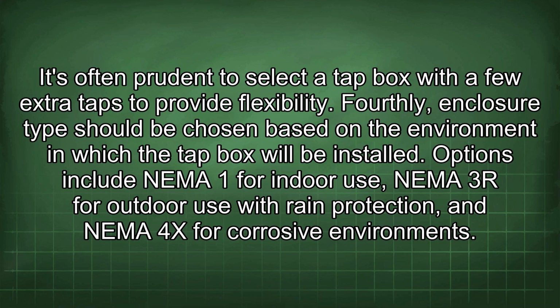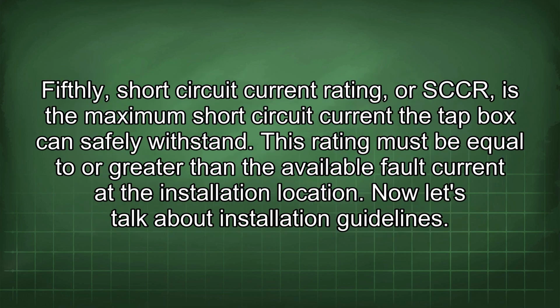Fourthly, enclosure type should be chosen based on the environment in which the tap box will be installed. Options include NEMA 1 for indoor use, NEMA 3R for outdoor use with rain protection, and NEMA 4X for corrosive environments. Fifthly, short circuit current rating, or SCCR, is the maximum short circuit current the tap box can safely withstand. This rating must be equal to or greater than the available fault current at the installation location.